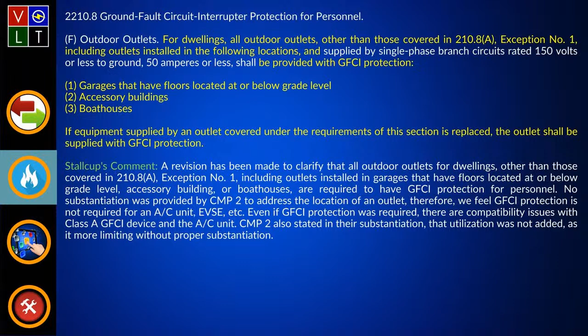So per 210.8, you would have to have GFCI protection for the receptacle, and then when you cord and plug connect it, the equipment itself has GFCI protection. He said he didn't need two, he only needed one.